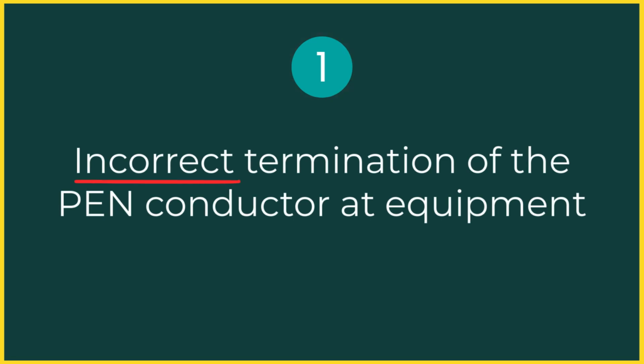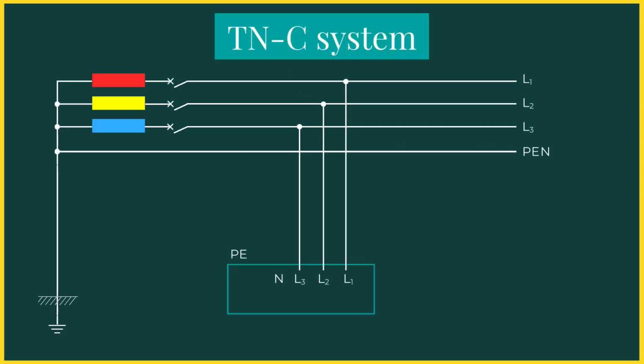Mistake 1. Incorrect termination of the PEN conductor at equipment. In a TNC system, the PEN conductor must always be connected first to the earthing terminal of the equipment. A dedicated jumper is then used to connect this earthing terminal to the neutral terminal. This ensures the protective function remains intact, even if the neutral terminal becomes loose. If the PEN conductor is connected directly to the neutral terminal instead, any interruption at the neutral terminal will also interrupt the protective earth. This defeats the basic safety principle of the TNC system.